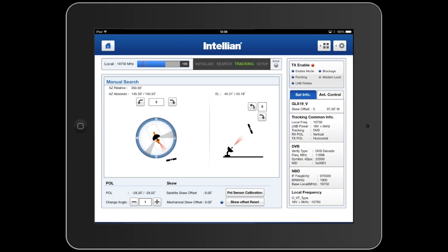For fine tuning, occasionally manual search is required. This screen allows us to adjust the steps and then adjust the elevation and azimuth of the antenna by small — in this case five degree — increments. Also within this screen, it's possible to set the pol sensor calibration as well as fine-tune the polarisation sensor angle.